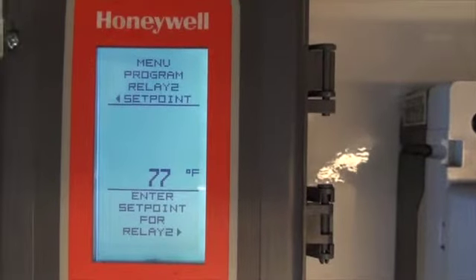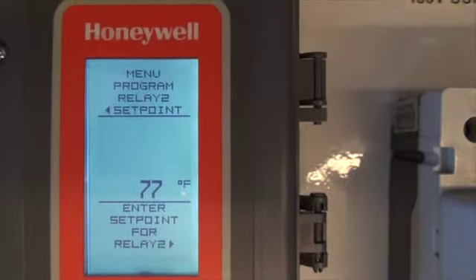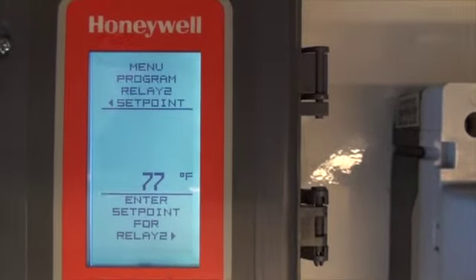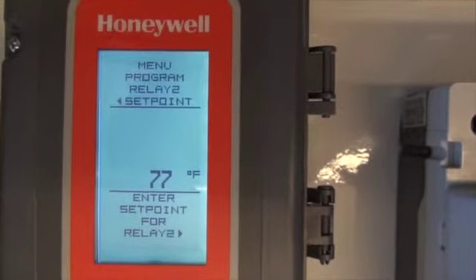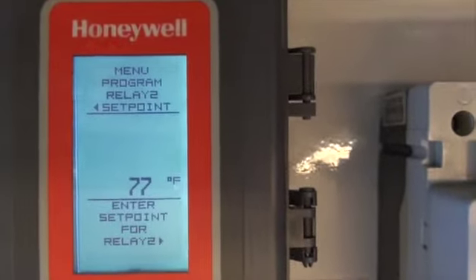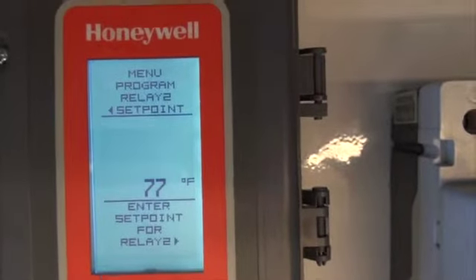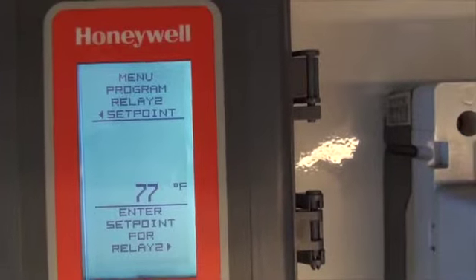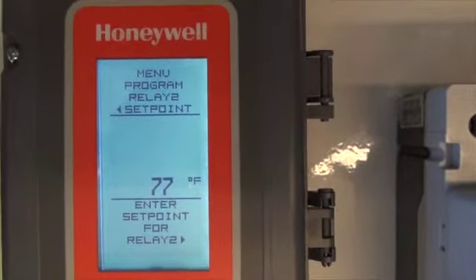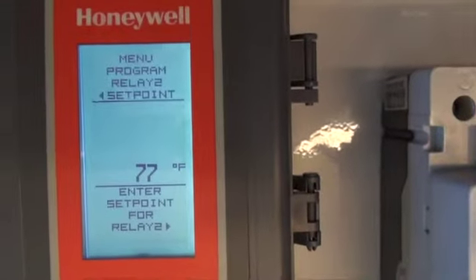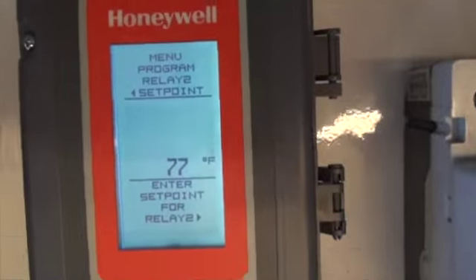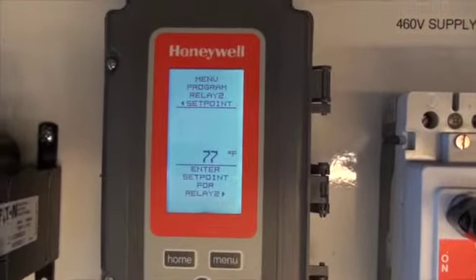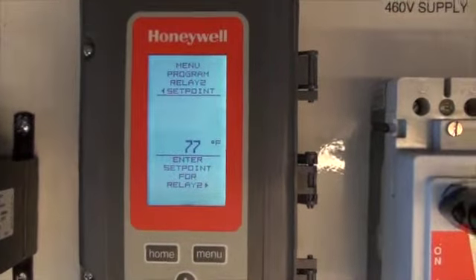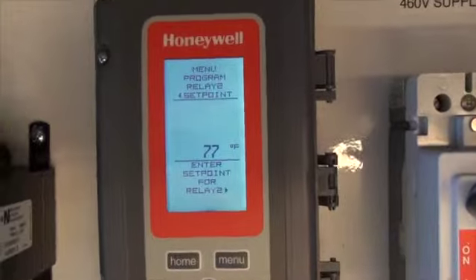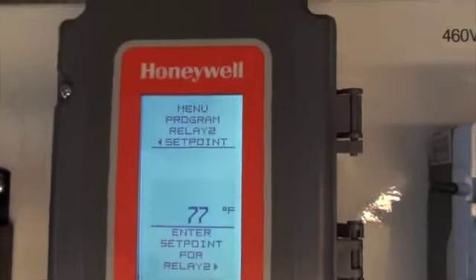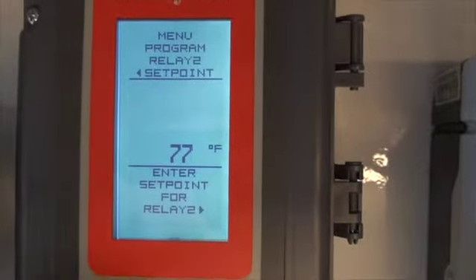It's key that that parameter is set a little bit above the throttling range. In other words, since I set an 80 degree process modulating set point temperature at 80 degrees and a throttling range of 10, meaning the drive starts to give a modulating output at 75 degrees, I want my drive to enable at about 77 degrees so that when the drive enables, it's not just sitting there at 0% output. It has a little bit of output, about 13%, so the drive doesn't start up and just sit there and grind at zero hertz. It goes up to about 15, 16 hertz. Anyway, so I set my relay 2 set point at about 77 degrees.